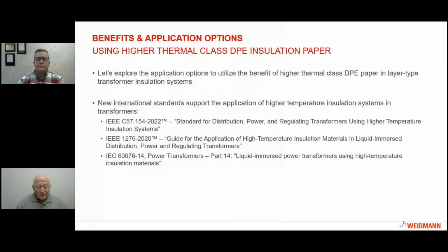Yeah, so after we introduce the specific features and some advantages of the enhanced insulating paper that we call DPE, let's explore the application options, how we can utilize this benefit of higher thermal class of DPE paper in layer type transformer insulation systems.